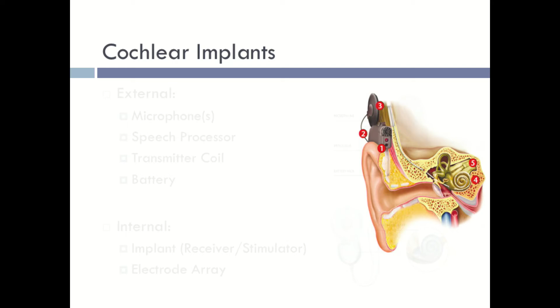So how does it work? Very simplified version. Sound is picked up via the microphone, and the speech processor is then converting that to specific patterns of electrical impulses. It's also doing a lot more with regard to identifying what exactly is speech in the environment, what is noise, how loud both of those signals are, and whether that noise is other people speaking. So it's a very sophisticated computer that's running most of the day.